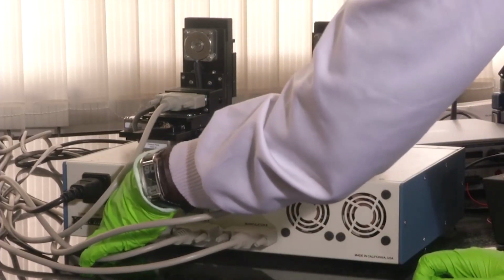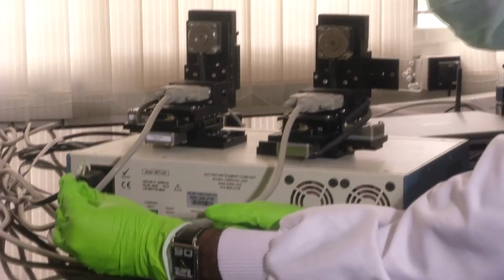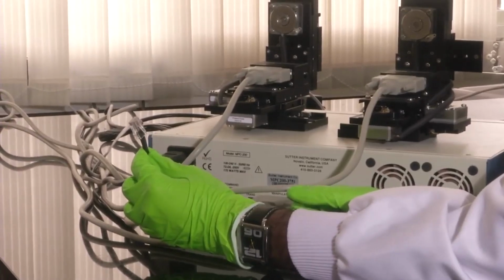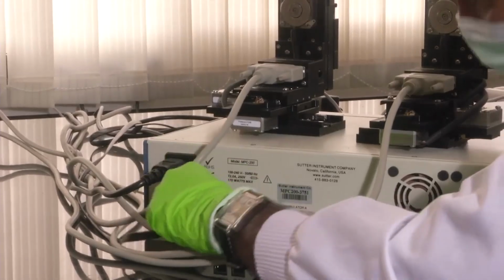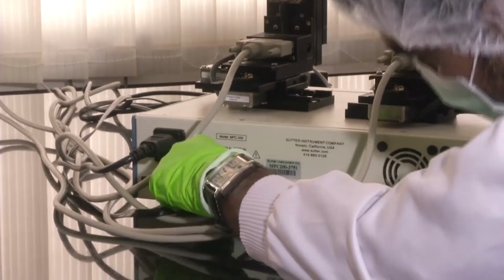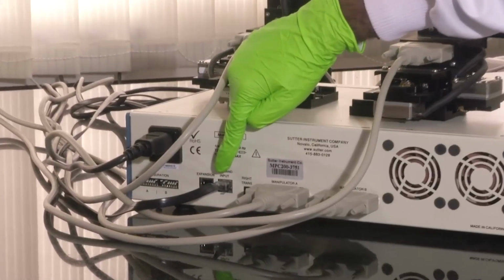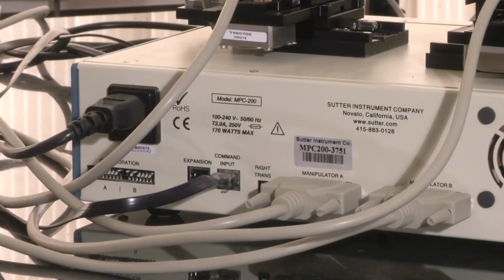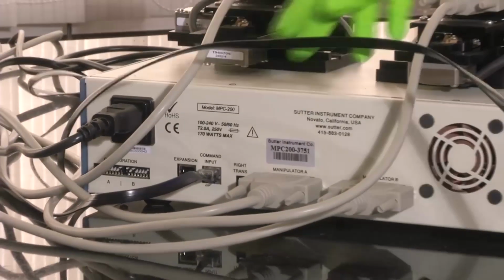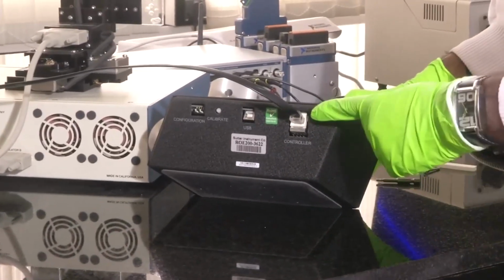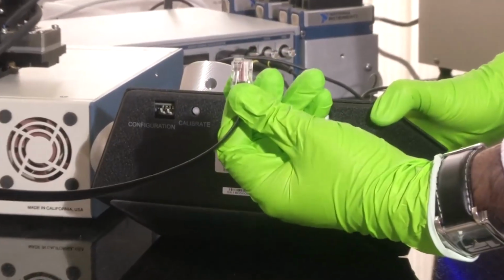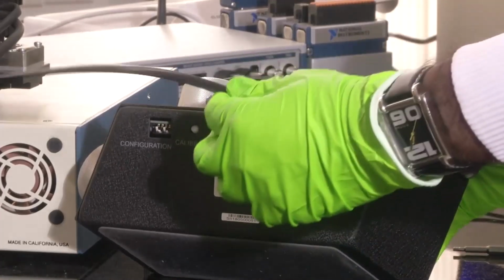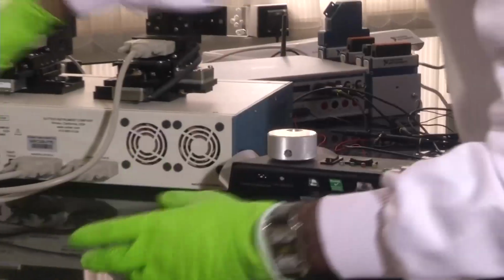If you see here, the command input port is an RJ45 connector. This RJ45 connector connects to the command input port of the manipulator. So, I have connected it back. Okay. This is the command input port. So, let me just show the control unit to you now. Okay. This is the back side of the control unit. This controller is again an RJ45 connector. So, the controller's control lines go from here, and the power for the controller also comes through these RJ45 lines. From this, the wire eventually goes around and finally ends up in the main unit.